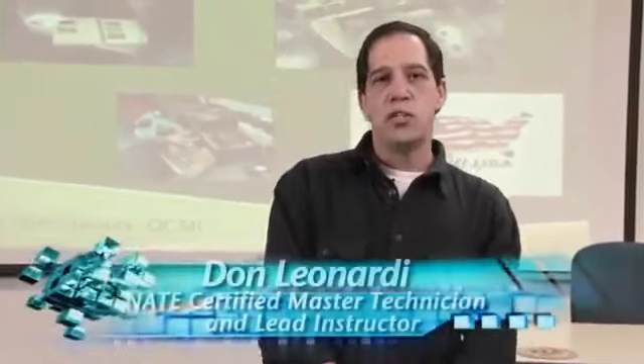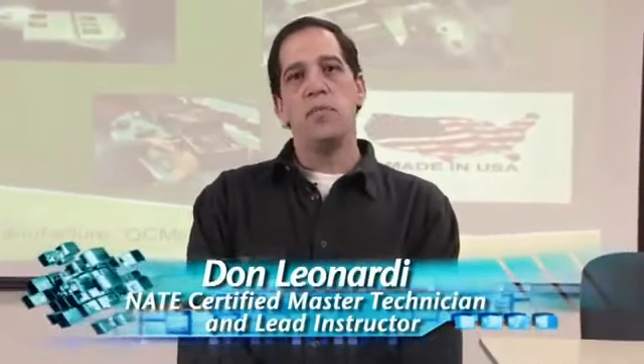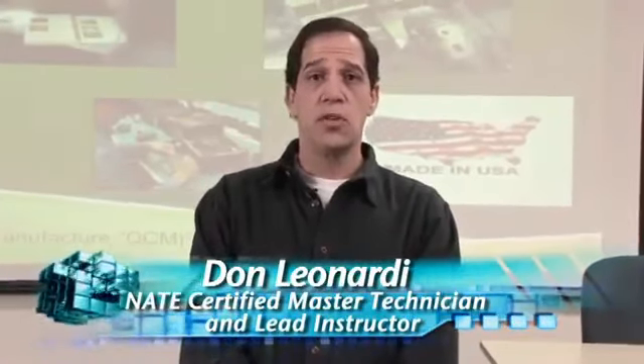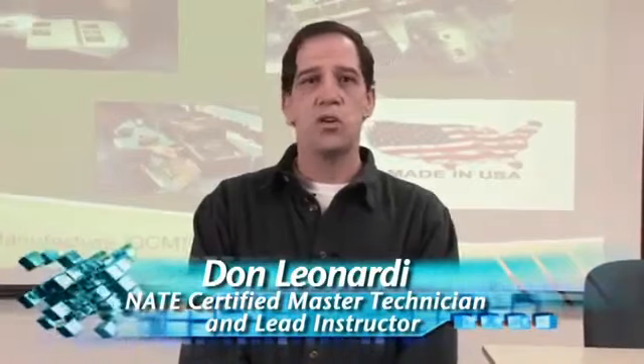Many times, as a 30-year technician in the industry, I've had people that have a hazardous condition within their space, whether it be CO or a smoke detector going off. I feel that one of the greatest benefits of the smart switch is to be able to shut our HVAC equipment down in the event of a contaminant such as CO and smoke in that space. Instead of just being a deterrent and kind of a hassle to the customer, at least we're assured that our equipment is shut down and that the family and the tenants are safe within the space.